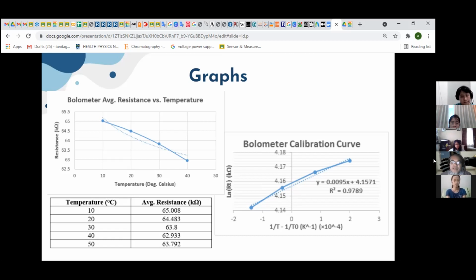And from this chart, there is a good trend, right? There is a possibility that it actually works. But it is also not convincing as data. You need to do at least 3 times of this data, multiple data. Similarly, you have to draw the standard deviation. Even within a single sensor, you have to do the calibration multiple times. You cannot just calibrate one time. At least 3 times, so that you can draw the standard deviation.